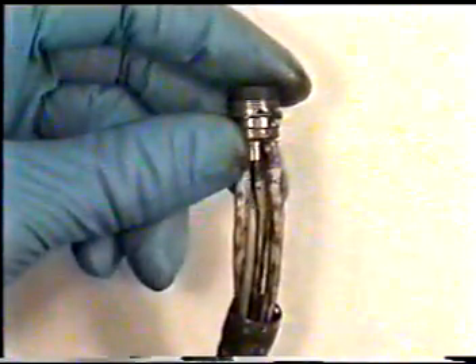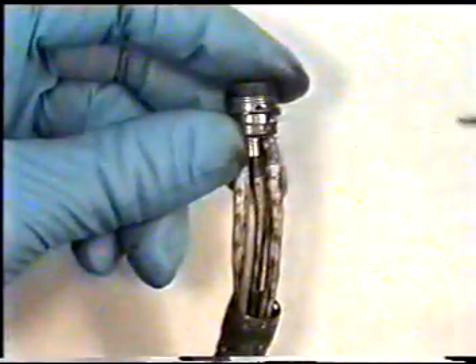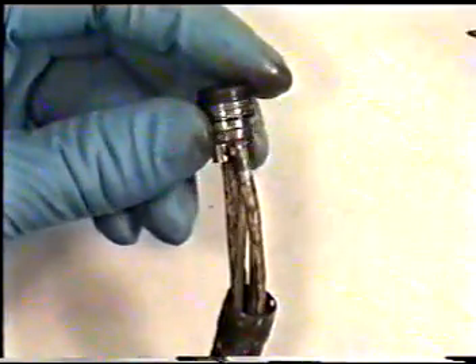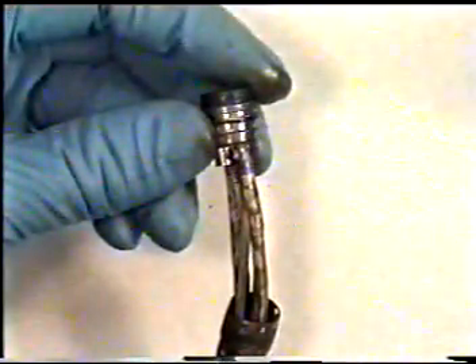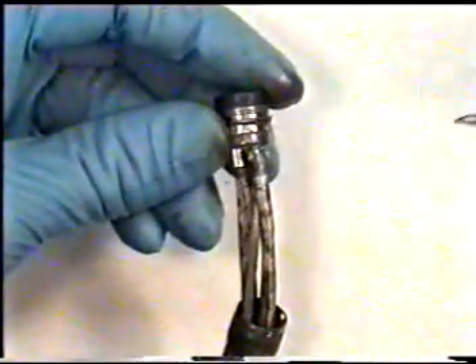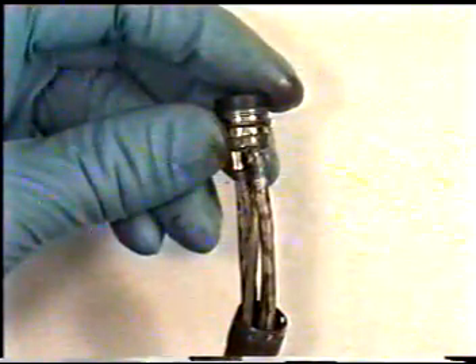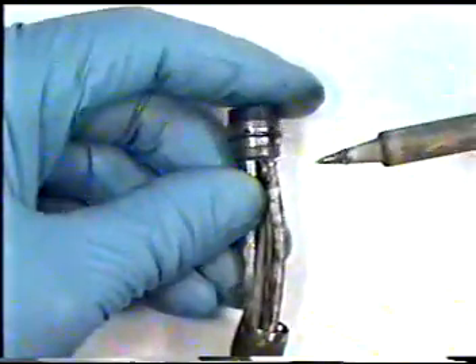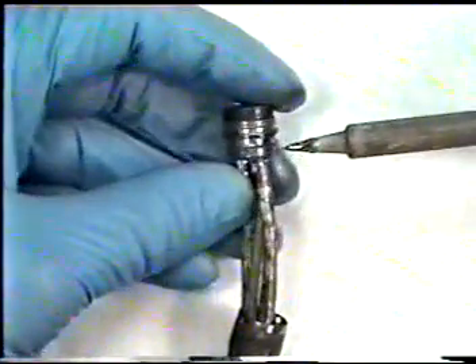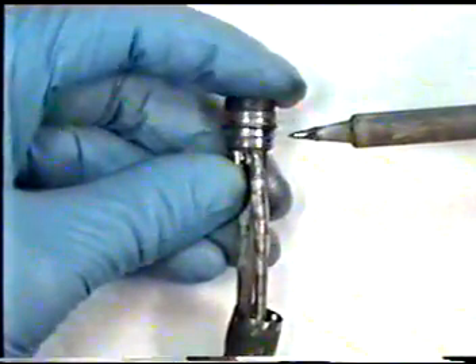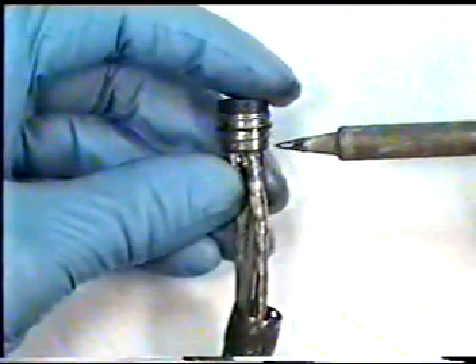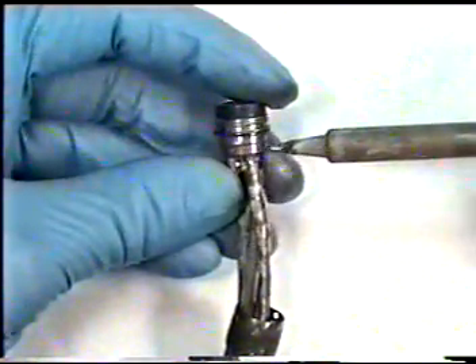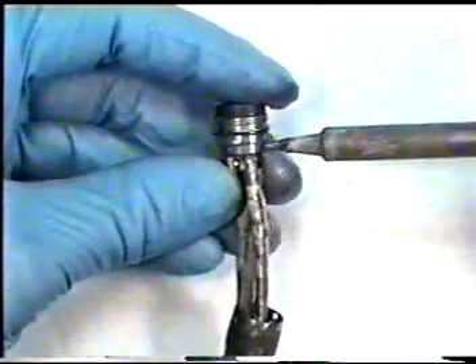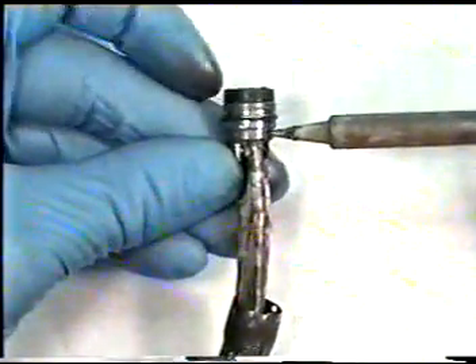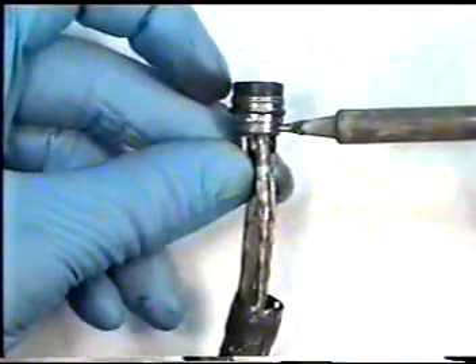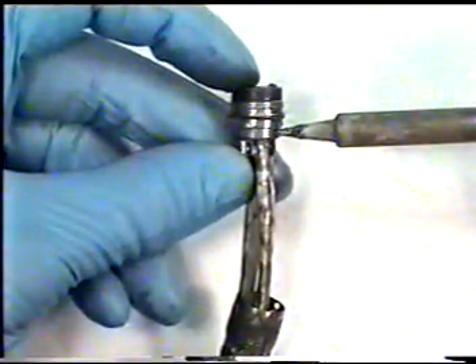In some extreme cases, it may be necessary to utilize a soldering iron tip. This will heat up your distal end in order to loosen the white glue from internally the distal end assembly. When using a soldering iron to heat your distal end assembly, it must be done in a very cautious and quick procedure. You will need to take your soldering iron tip, make sure that it is hot, and apply the tip in the hole where you had removed your light guide bundle set screws. The tip will get hot, so be careful of your fingers so as not to burn yourself. You will need to do this quickly.